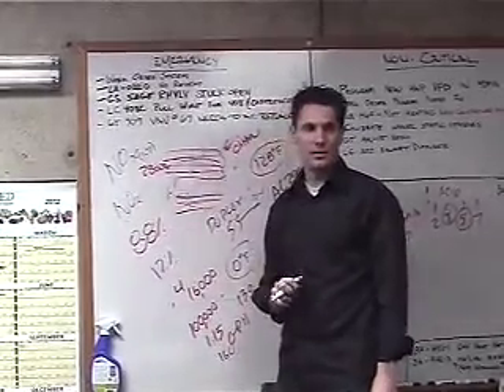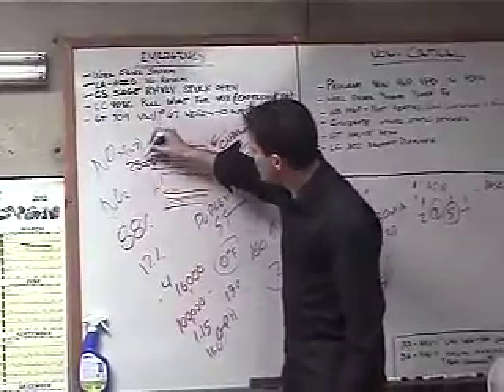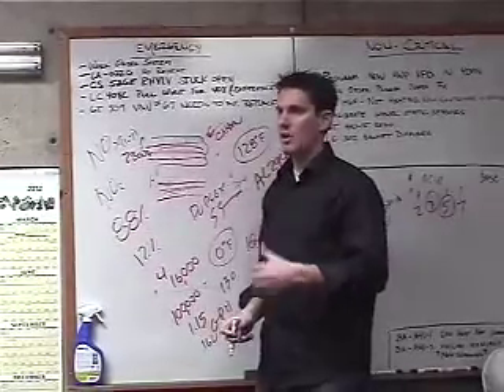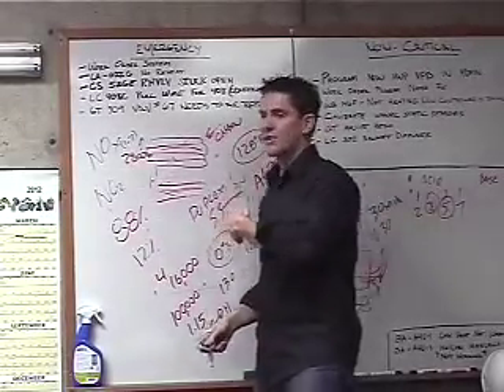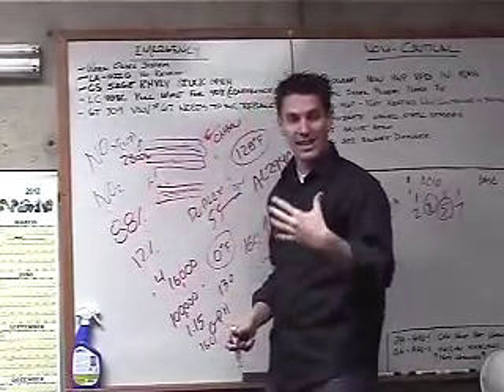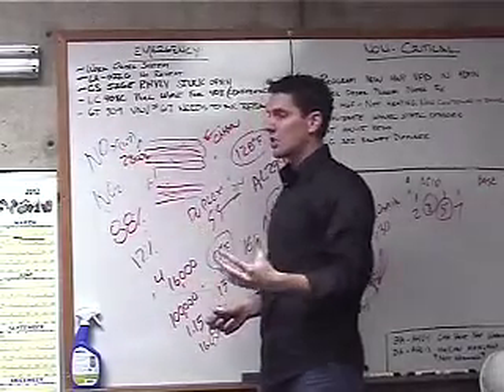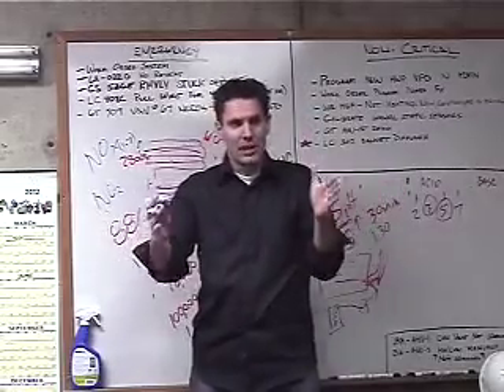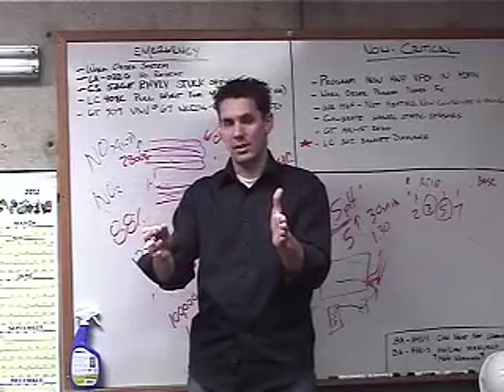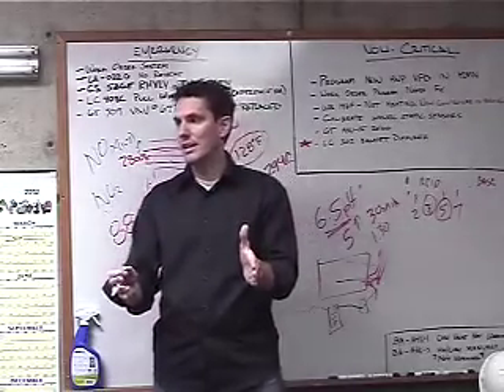The EPA regulates nitrogen dioxide, NO2. So if I have very hot flame temperatures in excess of 2,800 degrees, we force a chemical reaction between the oxygen and the nitrogen, creating more NOx. So we can't do that, so we have to subcool our temperatures. So I add more oxygen, I add more air, that excess air I mentioned, that 10-to-1 ratio. I add more air to cool my flame temperatures to prevent my pollutants. Okay, that's good, but I just decreased that limit, or that difference between my hot flame and my water. I made it smaller, so I'm less efficient. So, if I start to run lean, because the wind's blowing, my efficiency goes down.